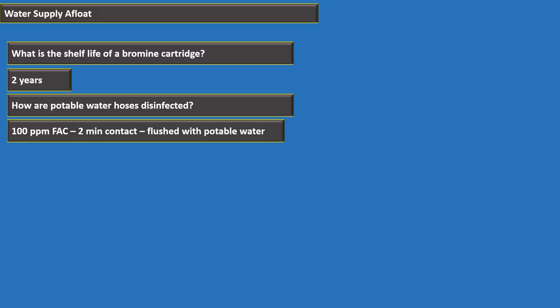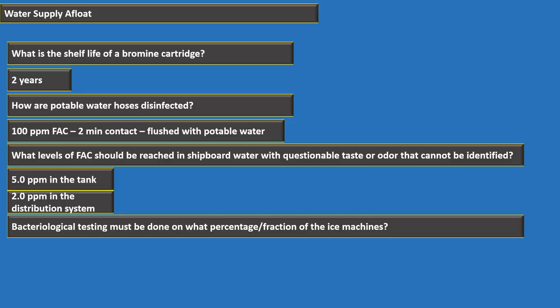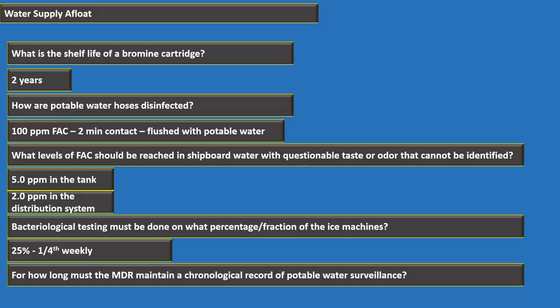For shipboard water with questionable taste or odor that cannot be identified, reach five parts per million in the tank and maintain two parts per million throughout the distribution system. Twenty-five percent of ice machines must be tested for bacteria weekly. The medical department representative must maintain a chronological record of potable water surveillance for two years.